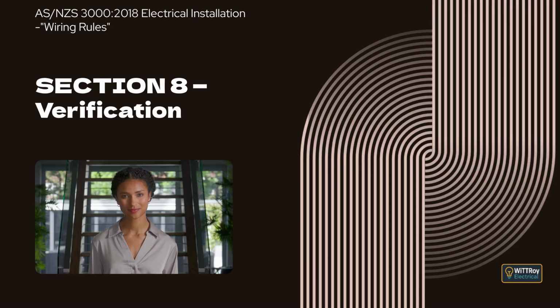Clause 8.3.9.2.3 No supply available. This clause explains the method used when supply is not available. In this case, the total resistance of the active and protective earthing conductors of the circuit is measured using an ohmmeter. Each active conductor and the protective earthing conductor are connected together at the origin of the circuit, usually at the protective device. The resistance of each active and protective earthing conductor pair is then measured at the furthest point of each branch of the circuit.